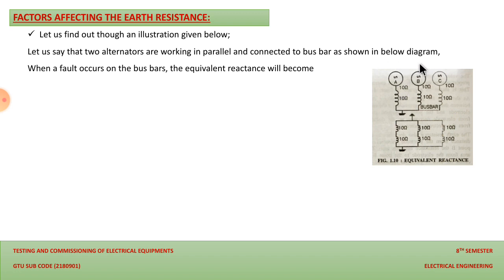When a fault occurs on the bus bar, the equivalent reactance will become, since these are in parallel, 1 upon X is equal to 1 upon X1 plus 1 upon X2. All have the same reactance, so that is 1 upon 20 plus 1 upon 20. So X becomes 10 ohm. Over here you can see that the reactance of the generator combination is 10 ohm.